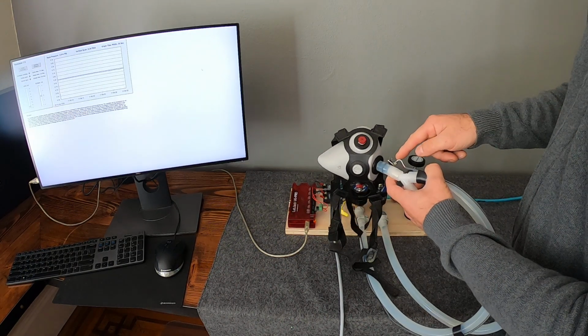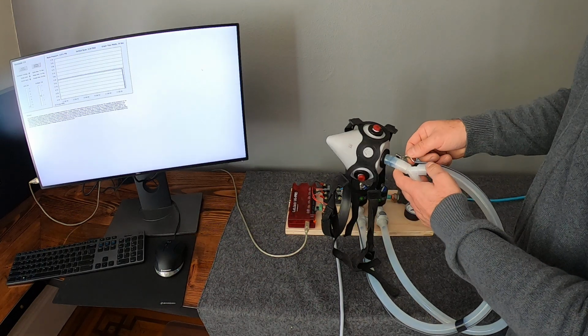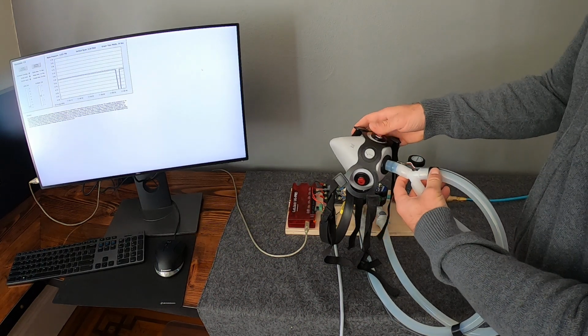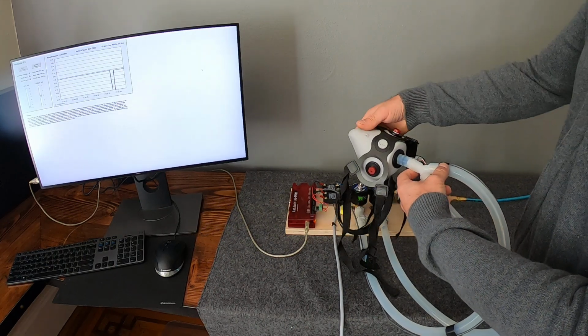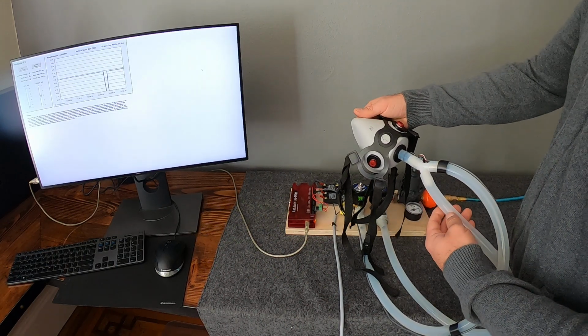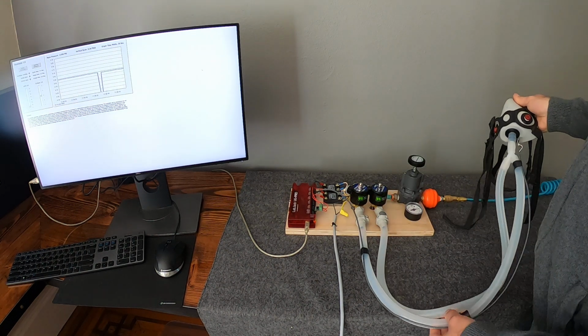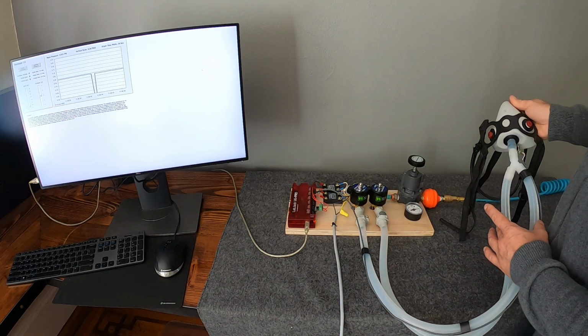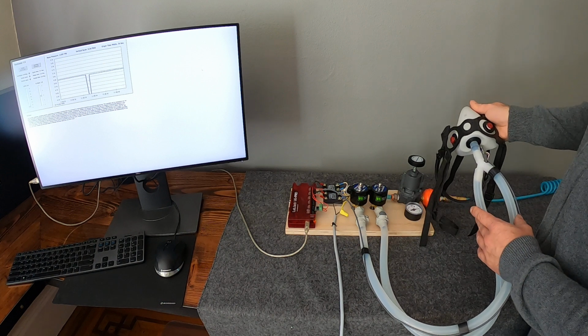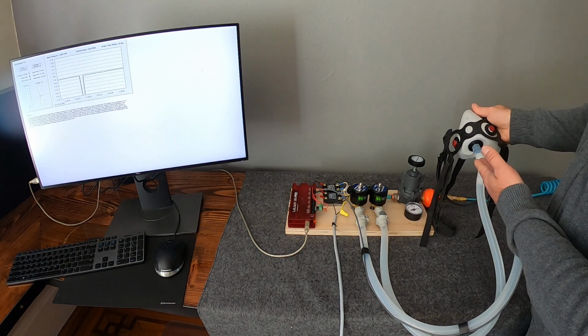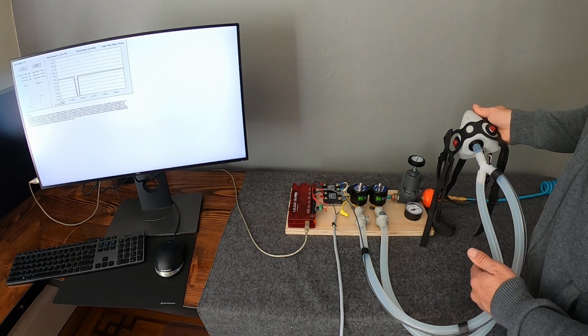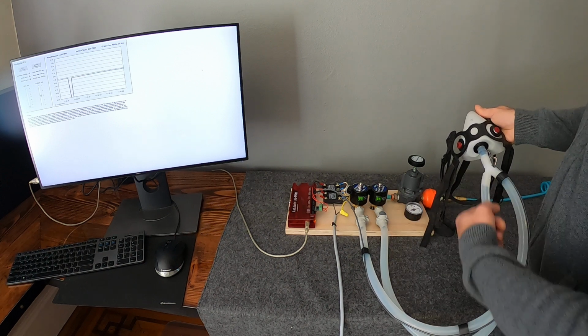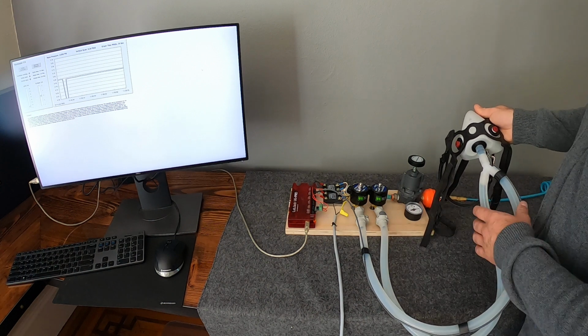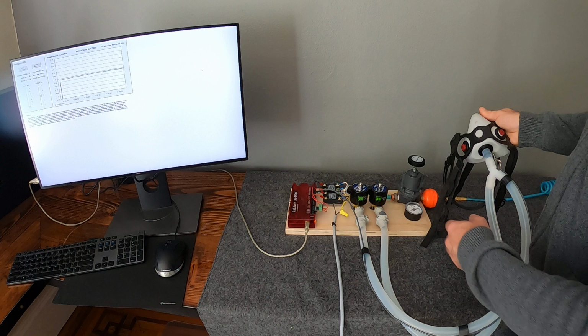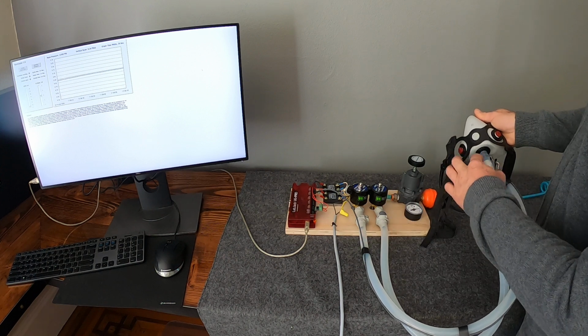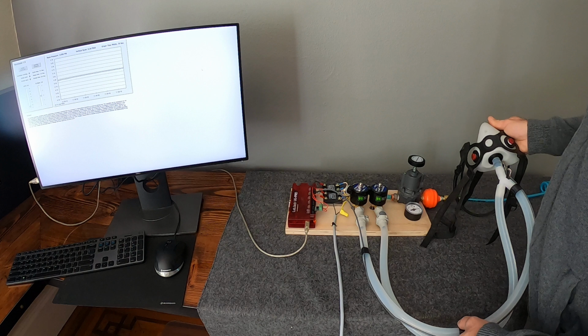The supply tubing's been fitted with this optional pressure sensor for monitoring the face mask pressure during use. That's not essential to use, but does provide useful information on how well it's functioning. The air is supplied and removed through two tubes. The use of two tubes is important as one only flows for inhalation and one flows for exhalation. This prevents recycling of air. That would be the case in a single tube. You would recycle exhaled air. So the use of two tubes and a Y adapter close to the mask creates smaller dead volume and prevents recycling of air.